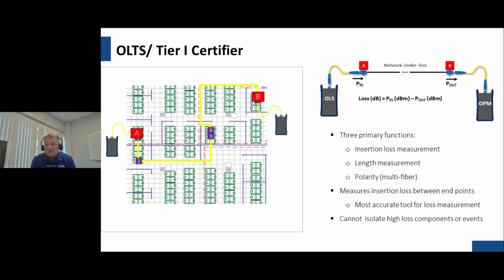So the OLTS allows us to measure the end-to-end insertion loss of that link. It'll provide the length measurement, which, as we'll see in a minute, becomes important when looking at different application standards that have a maximum length or typical length within a data hall. And then polarity, which becomes important especially in a link like this with several segments, where there's the possibility one of these links might have the wrong polarity, and that's a problem—so the ability to actually document and indicate what the polarity is.